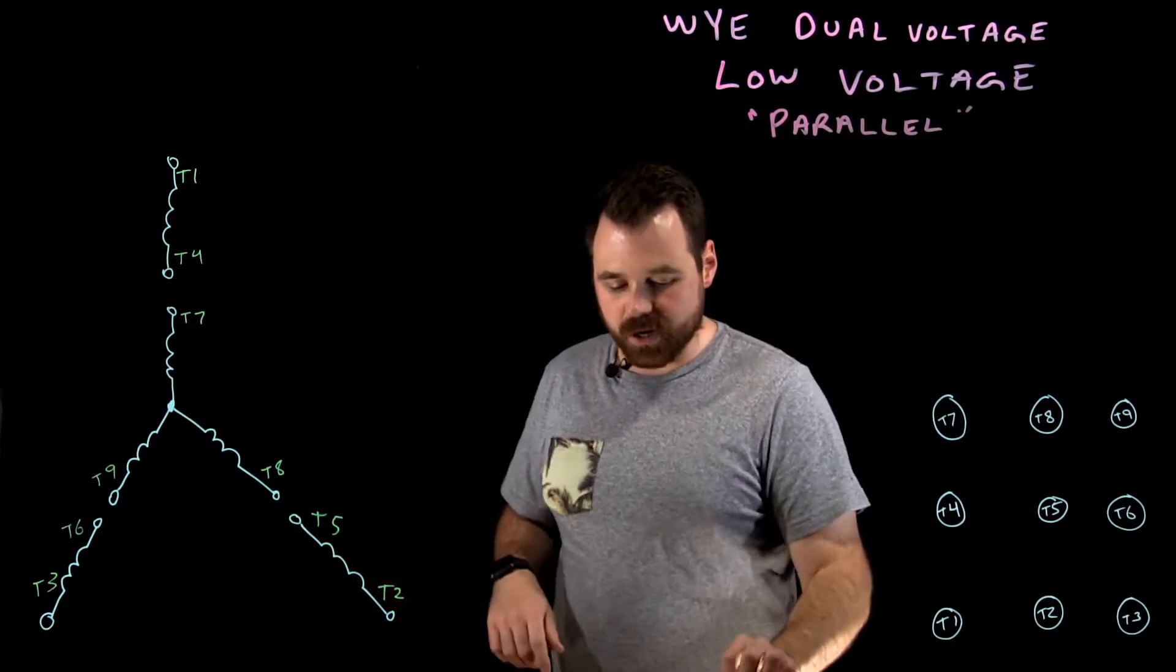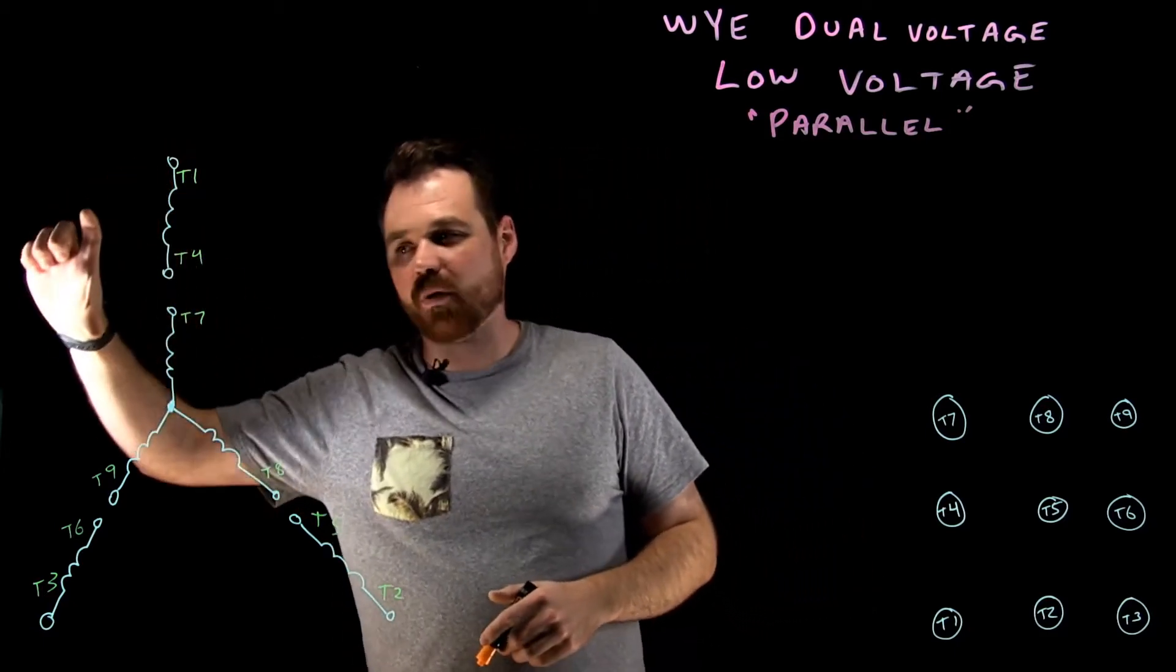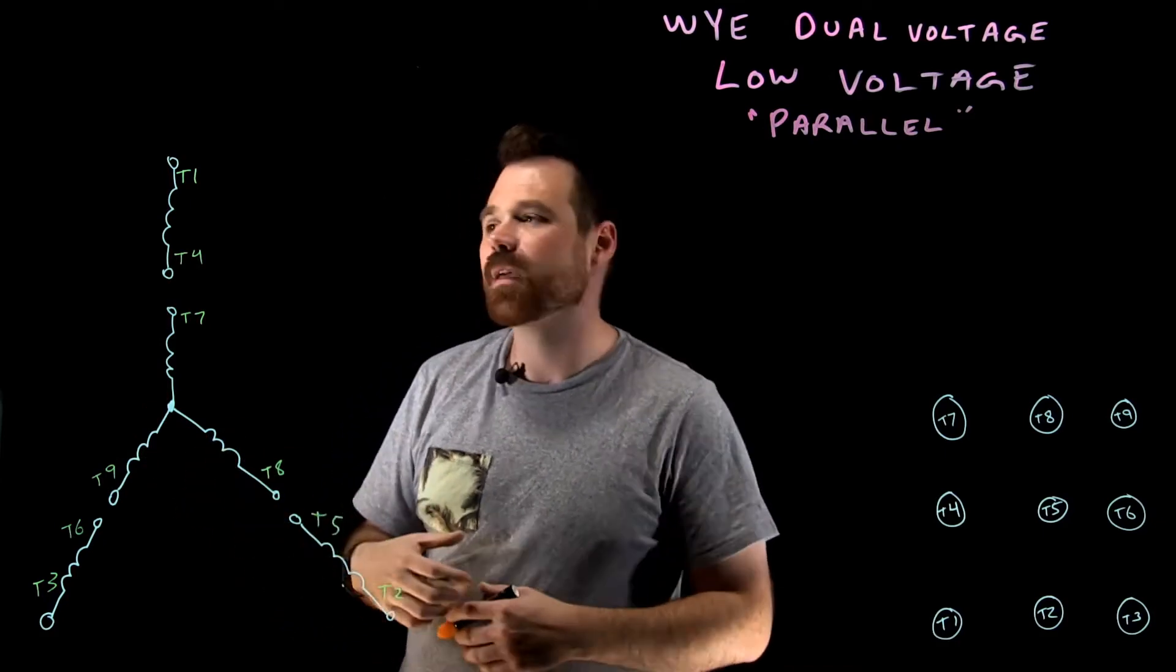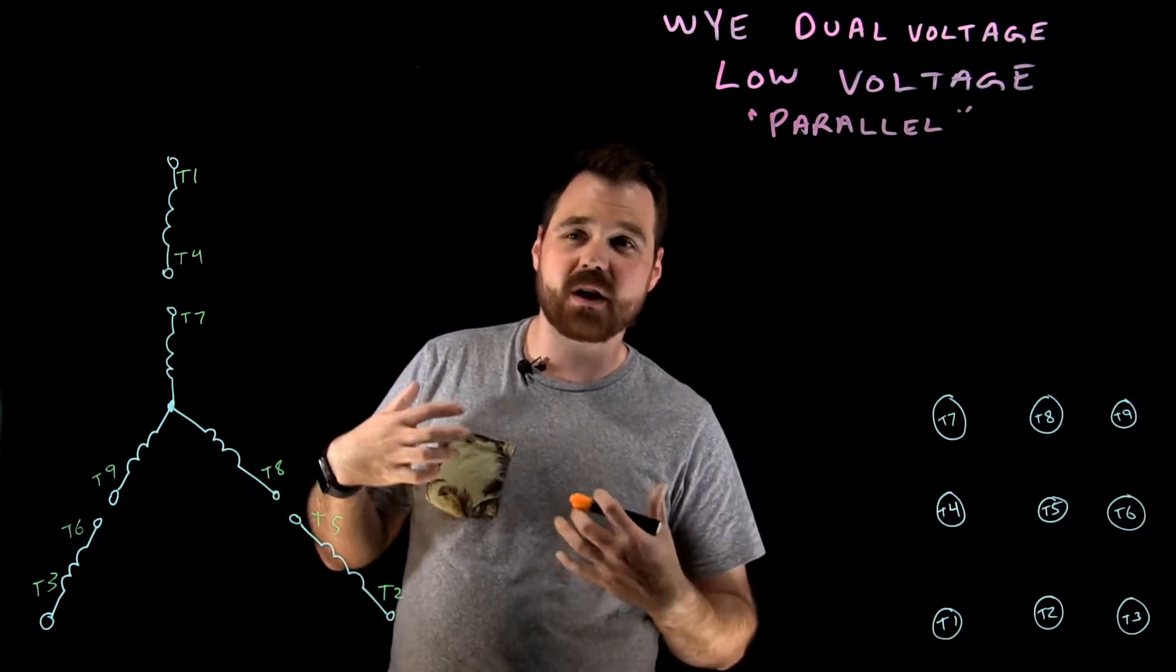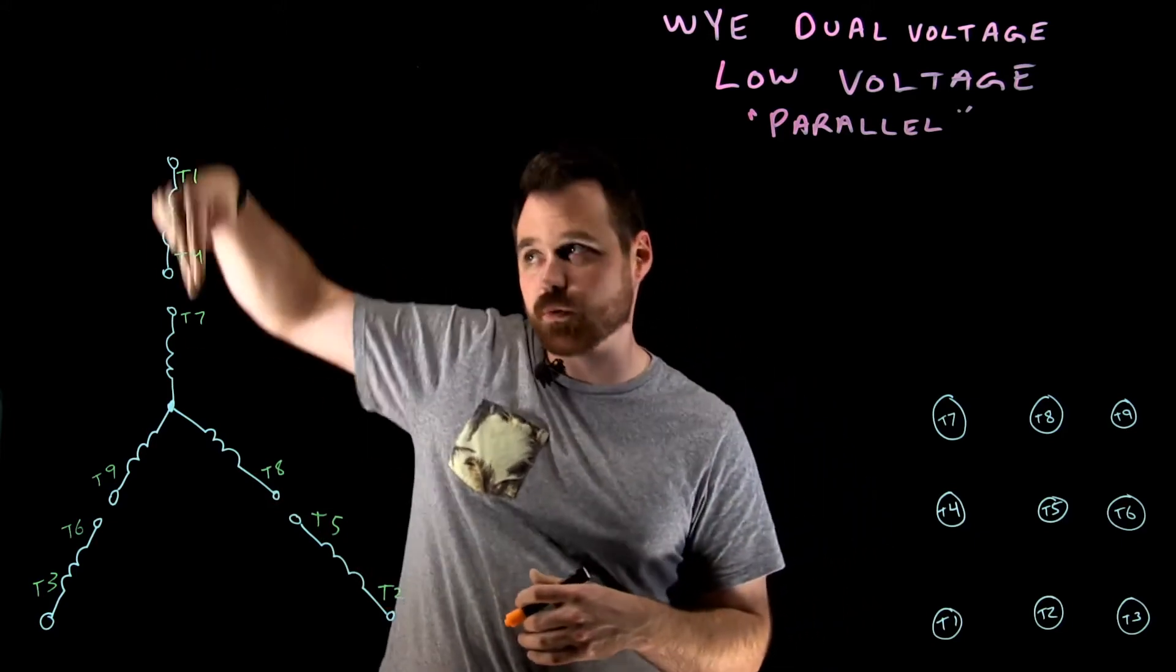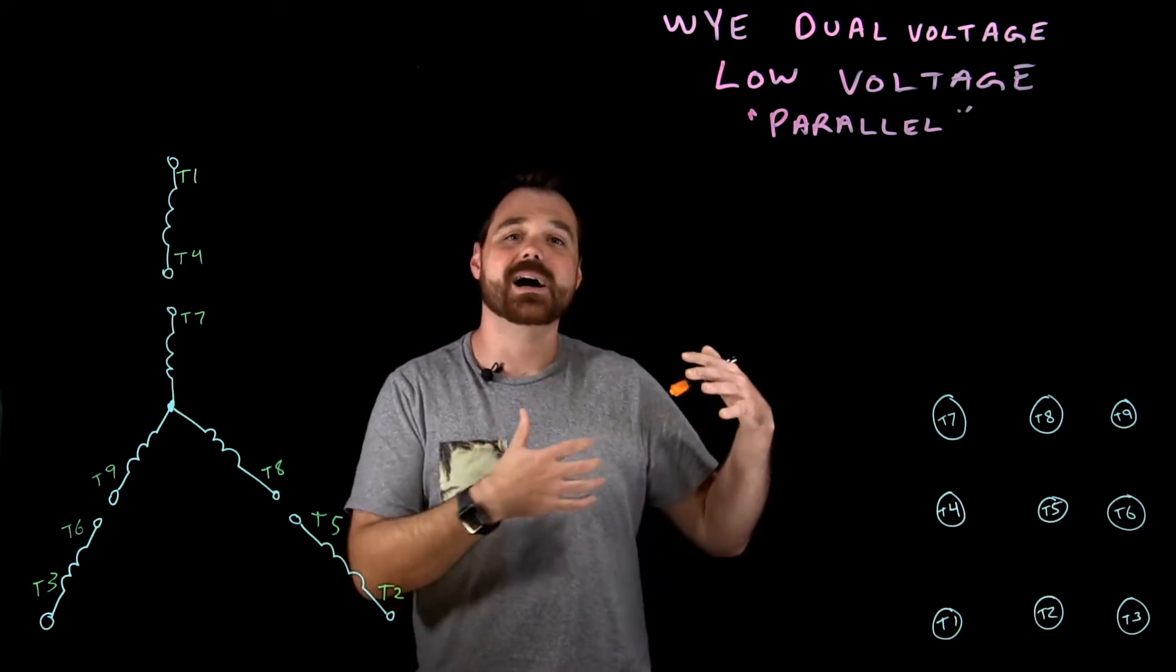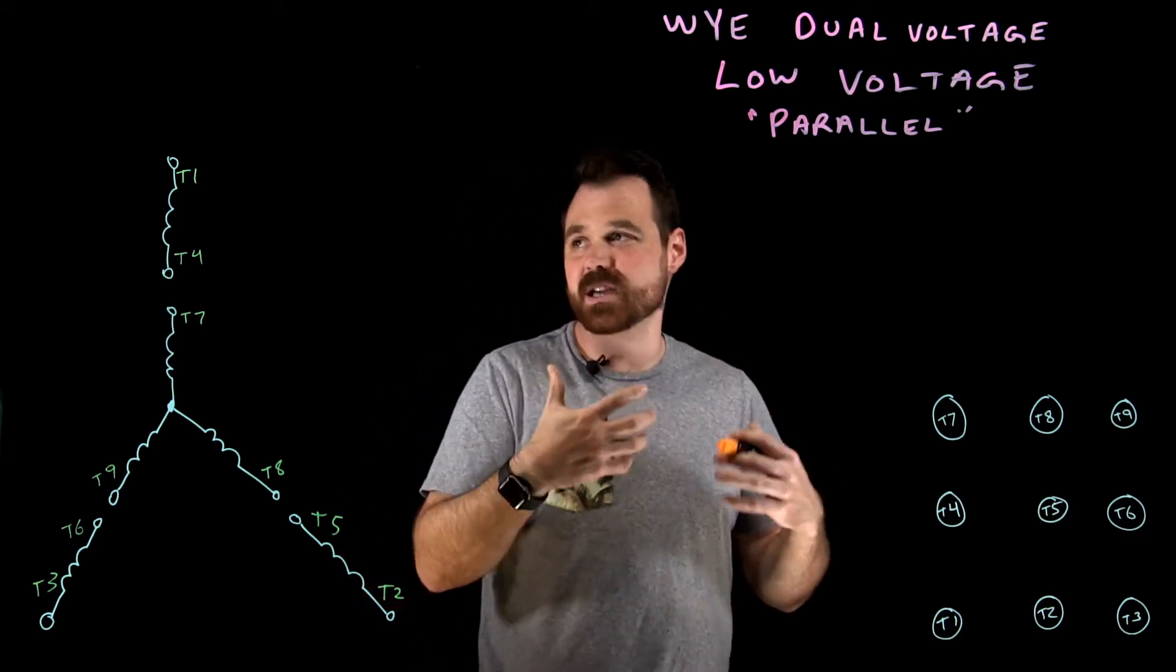Now what I want to do here is put this T1 and T4 winding in parallel with my T7 and T10 winding. Because they're going in parallel, it's really important that we keep the polarity matching so that current flows through them in the same direction, ensuring that the rotating magnetic field stays constant.